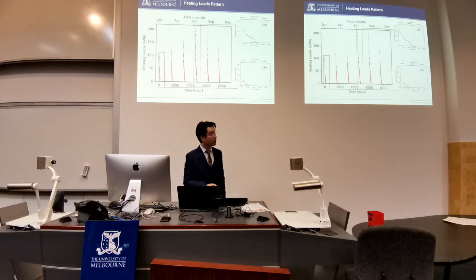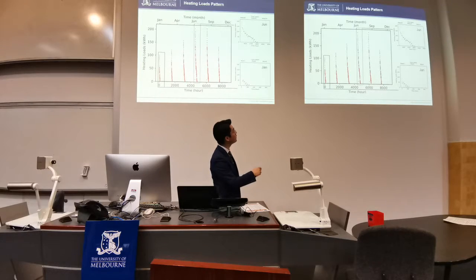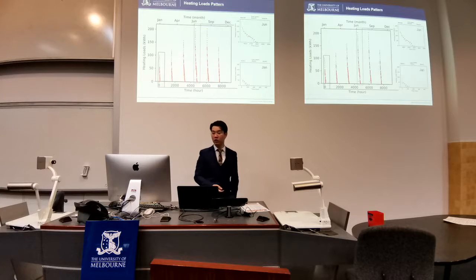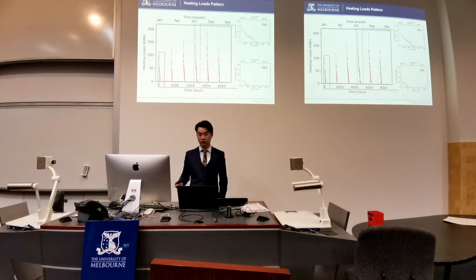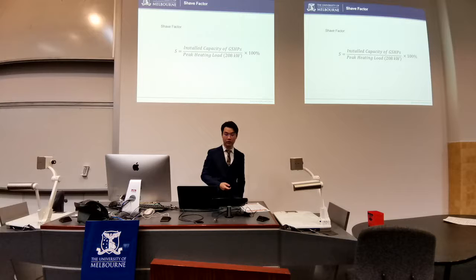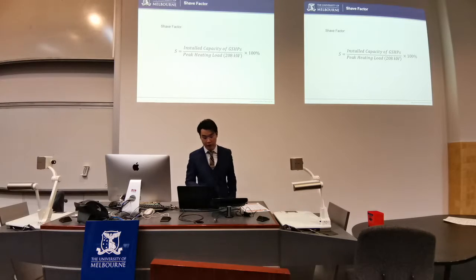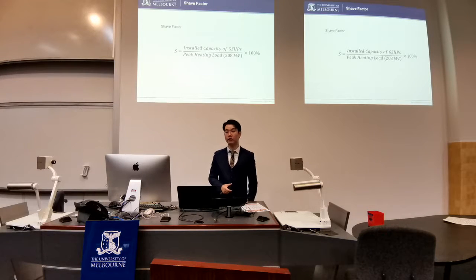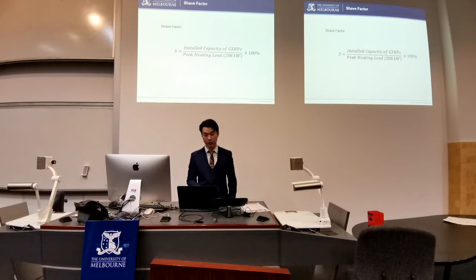What we can also observe from this figure is that for most of the time the heating load is relatively low. We could see that even if the peak load is over 200 kilowatts, for most of the time it's probably lower than 100 kilowatts. So what we can do about that is introduce a definition called shave factor, which is defined as the installed capacity of ground source heat pumps divided by the peak heating load. In our case, it's 208 kilowatts.